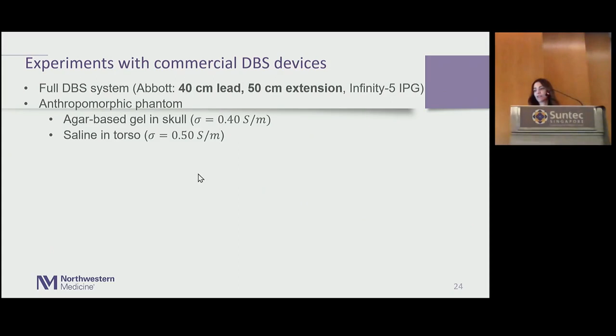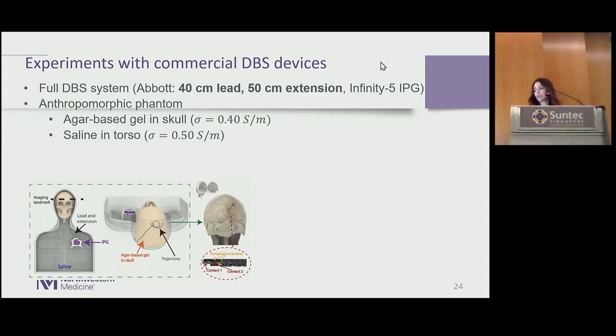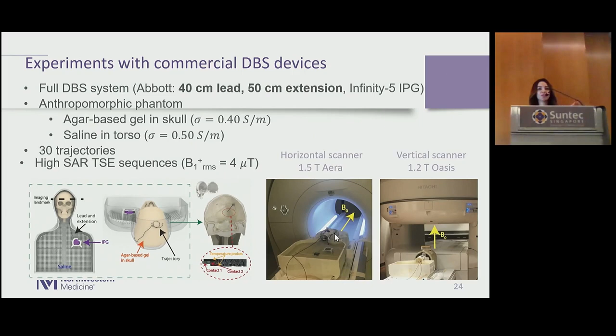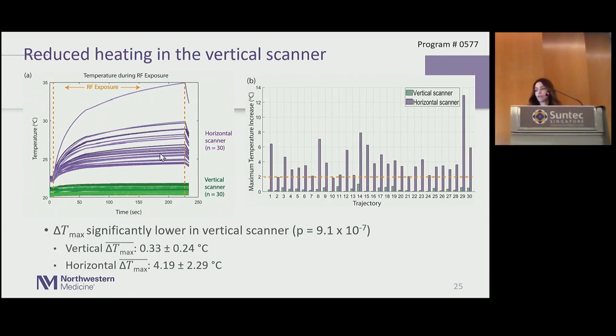You always have to go and actually do stuff in the scanner. So we worked with some medical device manufacturers. We got a commercial deep brain stimulation device. We created this anthropomorphic phantom that basically mimics the human body shape and material, because it's a multi-material phantom. And we scanned the device, and with optic probe, we could actually really measure the amount of heating that happens. And this is the results of comparison. These are actual experimental results in the scanner. Again, as you can see, more than 4 times, actually more than around 10 times reduction in the mean of RF heating.